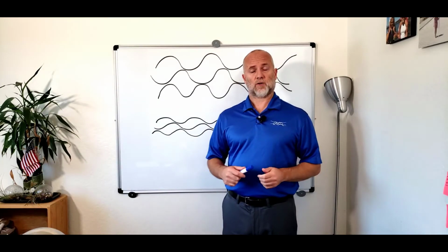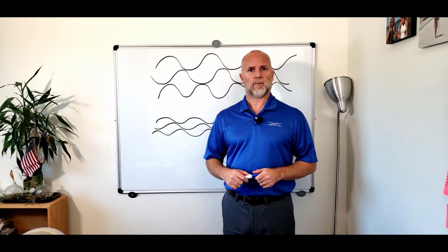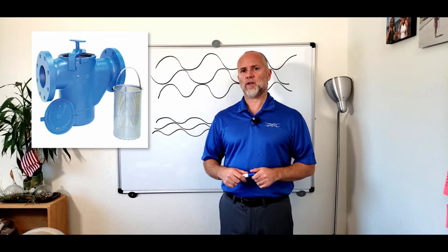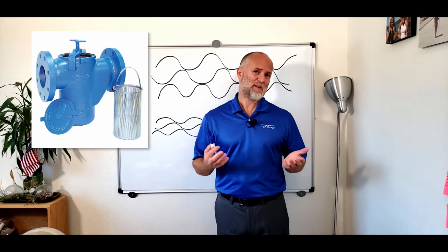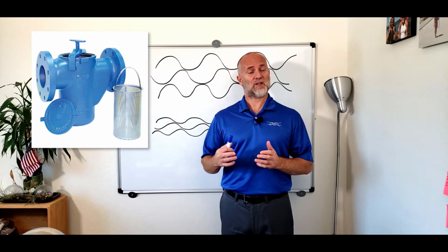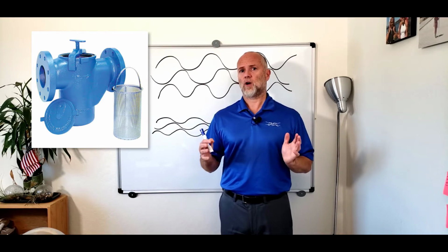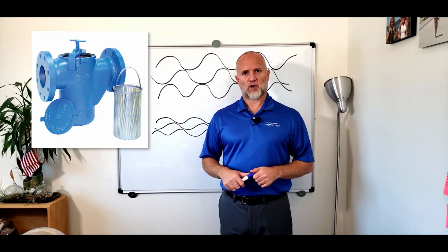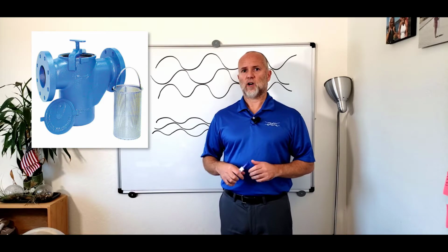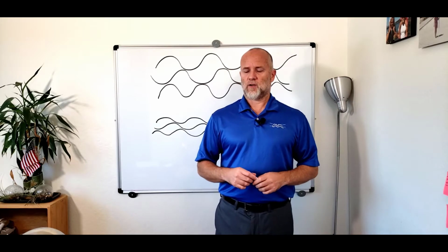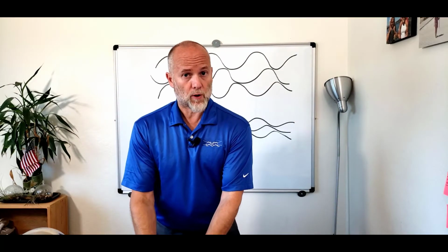The most common solution used for a cooling system are strainers. And strainers are, of course, a good solution. The main challenge that we see, speaking about plate and frame heat exchangers and strainers, is that in order to design the right mesh, you need to know the size of the channels inside of your heat exchanger. And that leads us to the concept of the pressing depth. We talked about the pressing depth in previous videos, but let's recap.